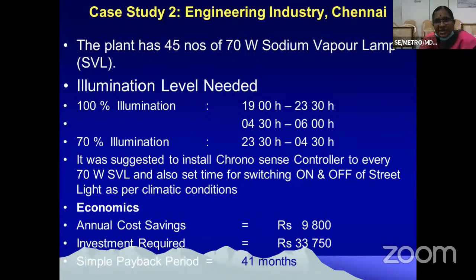In an engineering industry at Chennai, the plant has 45 numbers of 70 watts sodium vapor lamps. Illumination level needed is 100% at all the peak hours, night 7 to 11:30, morning 4:30 to 6. And from 11 to 4:30, they want 70% illumination. It was suggested to install a ChronoSense controller for the 70 watts SVL and also set time for switching on and switching off, so the light follows the climatic condition. Annual cost savings was around rupees 9,800. Investment required 33,750. Simple payback period is around 41 months. So use light wherever required, on and off according to the climatic condition.